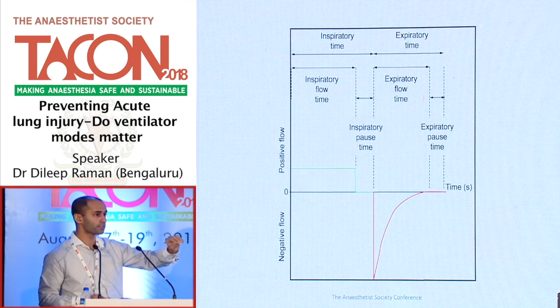Now, when you put an inspiratory pause between inspiration and expiration, you achieve zero flow. When you have zero flow, that's your plateau pressure. So you all know this: you do an inspiratory hold, you get this. You can also set this on a GE vent or any other vent by setting the inspiratory pause percentage. When you have an inspiratory pause, the ventilator will show you what the plateau pressure is. Some of the ventilators will allow you to set an alarm to that plateau pressure. As long as you have the alarm functioning, you will always know if you've hit an injurious plateau pressure.